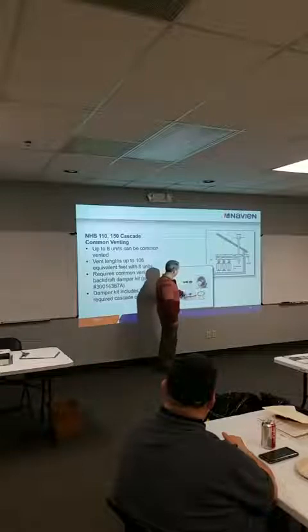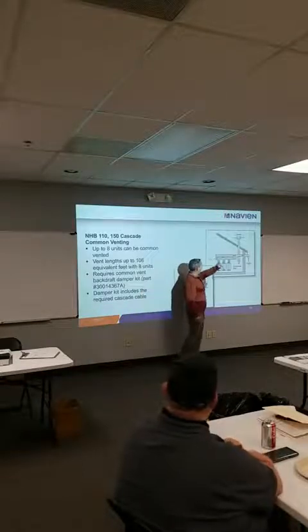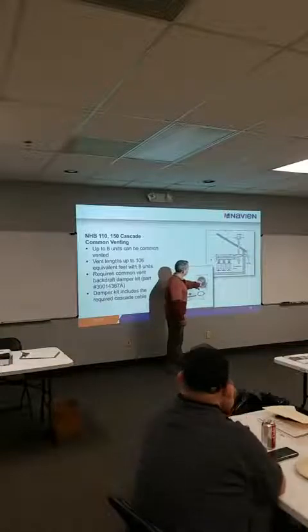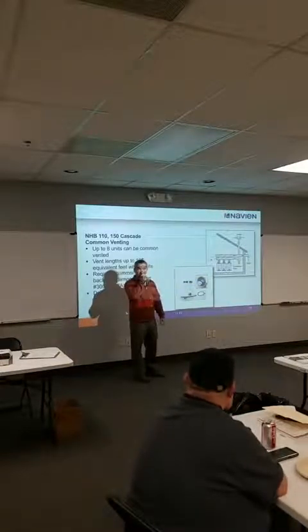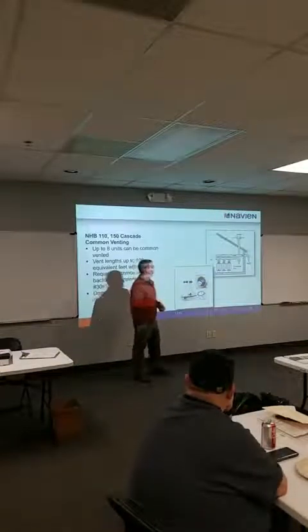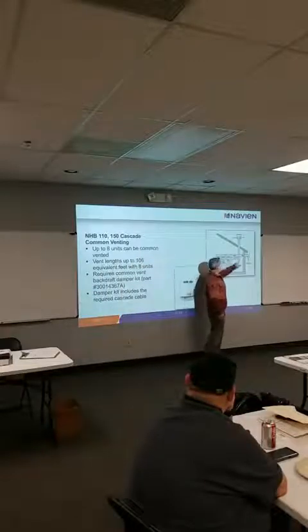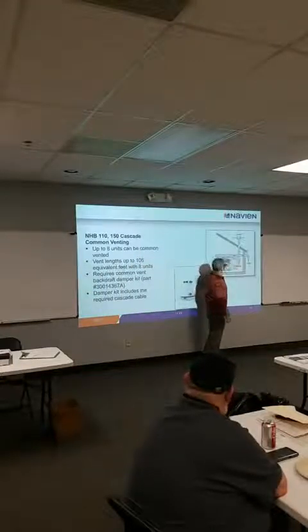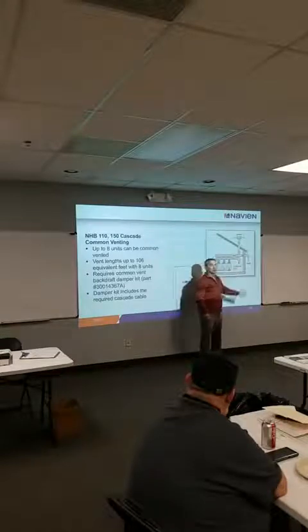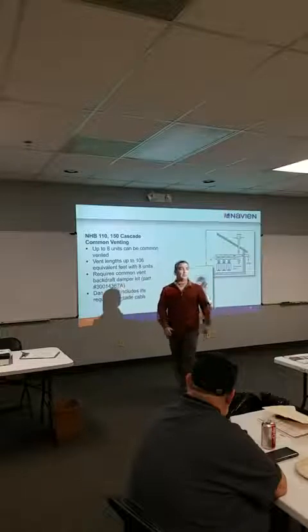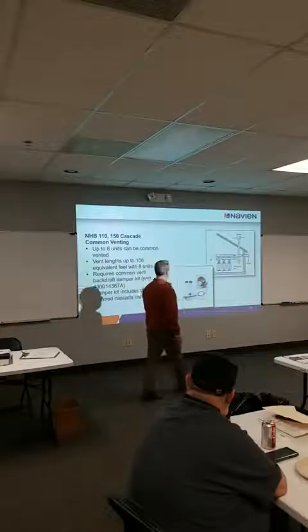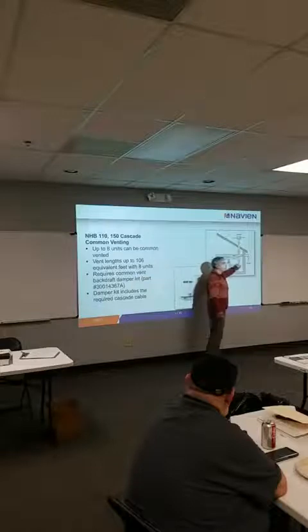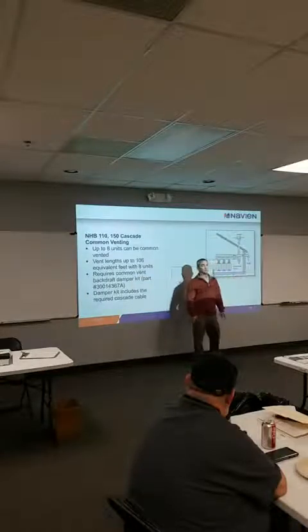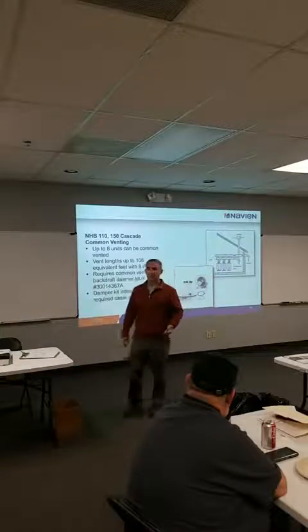This vent damper goes in place of your vent collar, but since it has a damper plate on it, you can't take the condensate back to the unit anymore. It'll just sit on that plate. So you need to put a condensate drain T in and drain your condensate, if it gets in the units here, back to this T and then everything out. Oh, so you run that back downhill to the unit? Yes, and then this line here, you have a little poly hose coming off that, and you do have to trap that, because there's no trap there right now. Again, that's in your manual.